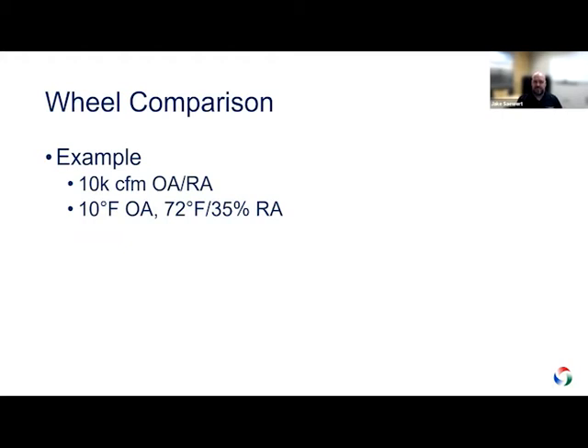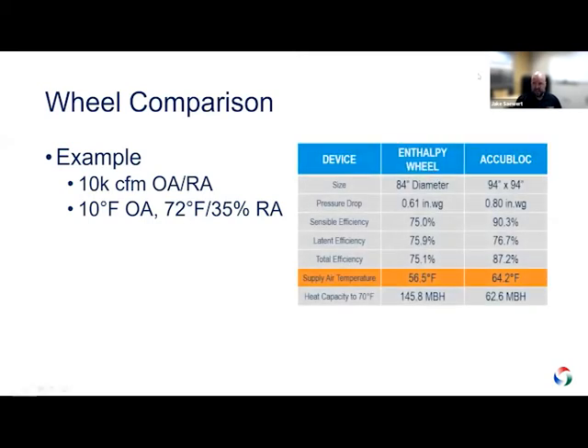Best way to show the performance of this is with comparing it to a wheel. You know, if I take a 10,000 CFM example at 10 degrees ambient, the reason I chose 10 is because that's typically close to the threshold of where below that a wheel might actually freeze, especially if a space is humidified. And I just use 72 degrees, 35% relative humidity coming off from the return. If you take a look at this performance, I ended up selecting about an 84-inch diameter wheel with 0.61 inches water gauge, so a little bit less than what we would do with an ACCUBLOC. The ACCUBLOC is larger at 94 by 94, has a little more pressure drop, but look at the sensible efficiency between these two. So we're talking 90% efficient. Yes, we could drive this up to get to 95%, but truthfully, the sweet spot in terms of overall cost is probably more around 90, 91% sensible. So I chose to do that with this selection.